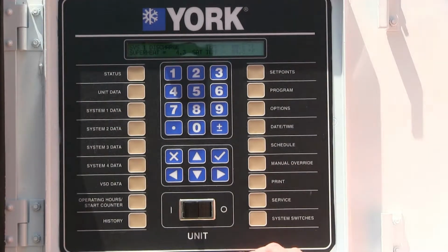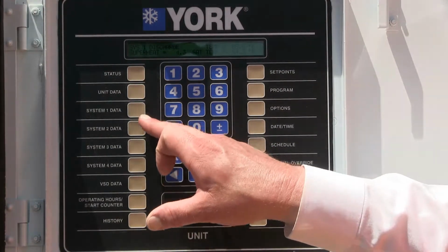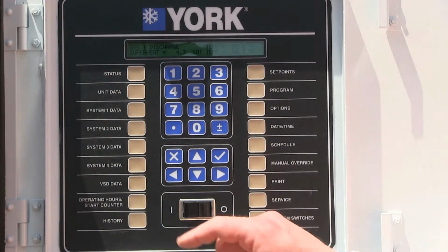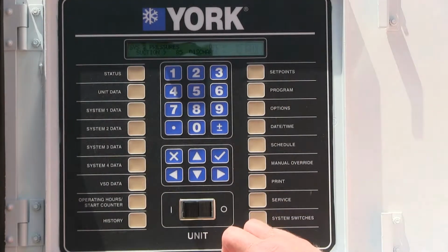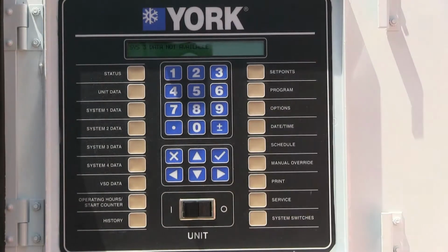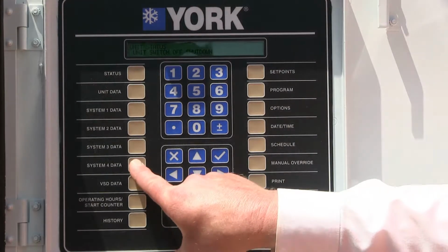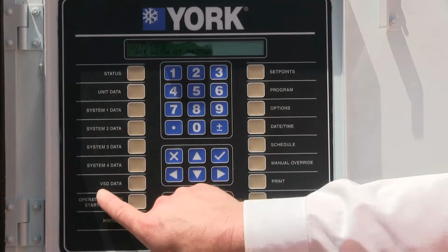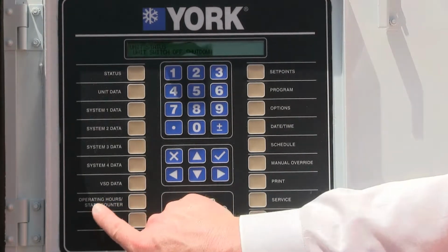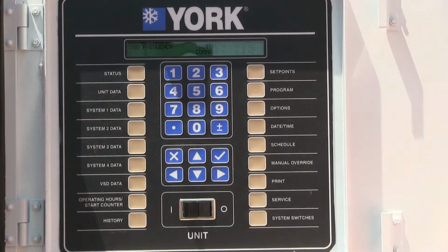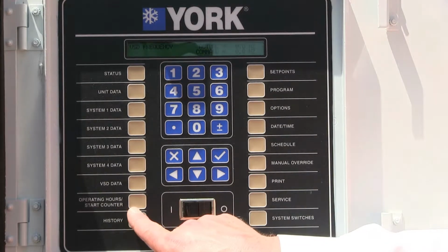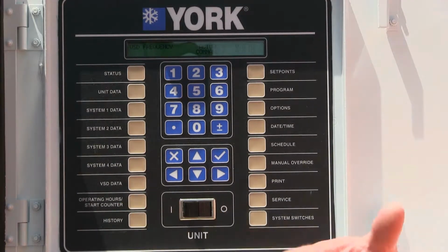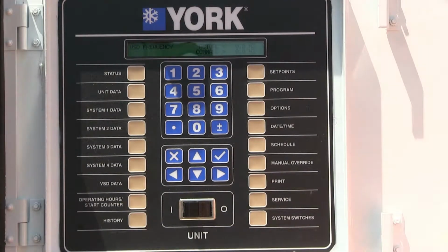This being a 200-ton chiller, it's got 2 circuits on it, system 1 and system 2. Each one of them is 100 tons, so you're going to have data underneath system number 2. System 3 and 4 are for larger tonnage chillers, so when you push those buttons, there's no data available because it doesn't require a 3rd and 4th compressor. The VSD data is your variable speed drive data, and this is where your hertz are going up and down as it's commanded off the variable speed drive. This machine does run completely off variable speed drives, allowing for infinite temperature control. Then you've got your operating hour and start counters. All that does is count how many times the machine started and stopped, and how many hours the compressors have run.